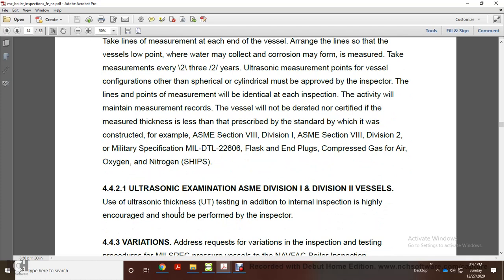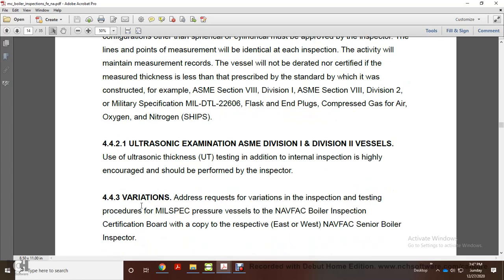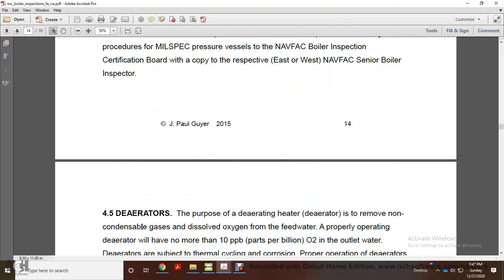4.4.2.1 Ultrasonic examination, ASME Division 1 and Division 2 vessels. Ultrasonic testing in addition to the internal inspection is highly encouraged and should be performed by the inspector. 4.4.3 Variations. Address requests for variation in inspection testing procedure from the military specification for pressure vessels to the NAVFAC boiler inspection certification board, with a copy to the East and West NAVFAC senior boiler inspectors.